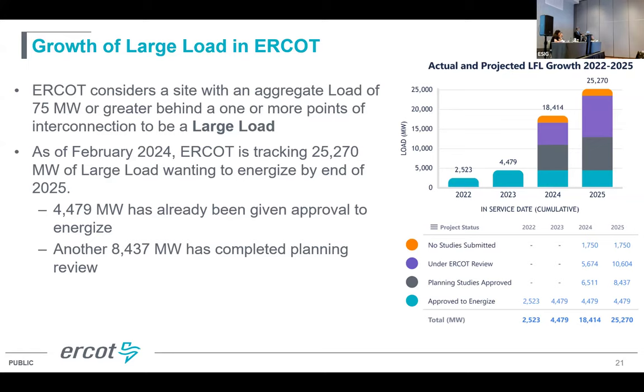Right now we have close to 4 gigawatts already connected to the system. For short-term projections, you can see what's in our queue: 25 gigawatts of this load. This is just the large loads, and it contains data centers, crypto loads, hydrogen loads, all of those. In addition, we are also seeing tremendous load growth, especially in West Texas, from oil and natural gas loads. Our planning cycle looks 6 years out. Last year, when we did the studies, our load projection for the furthest year, 2029, was 120 gigawatts.